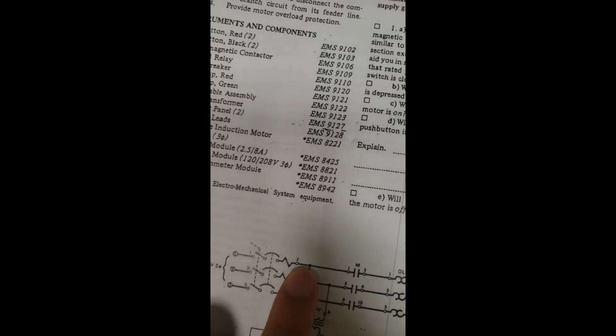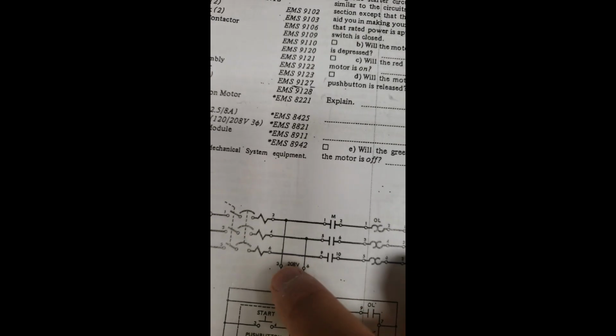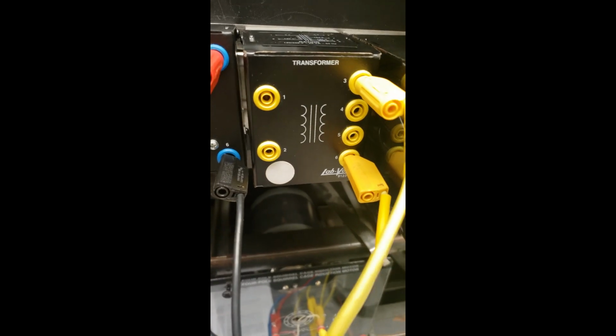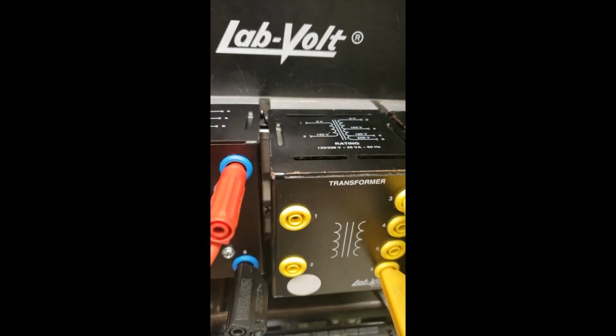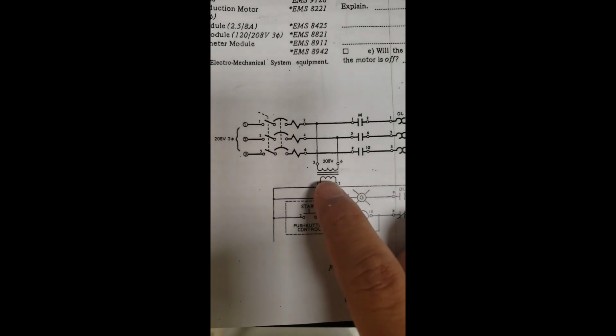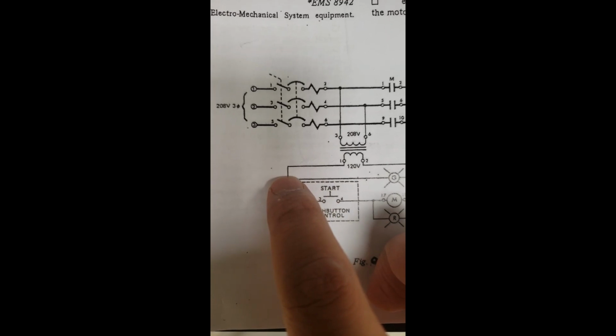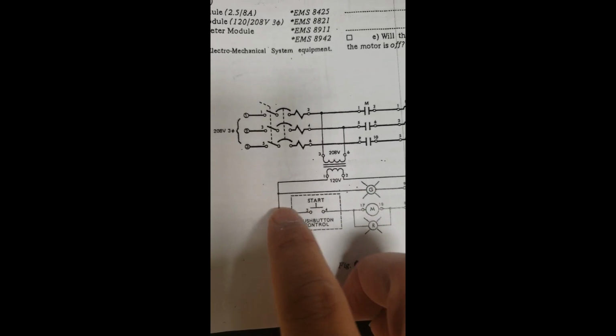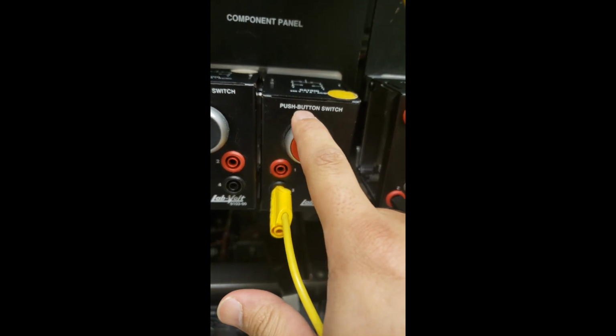Then from 1 and 5 of the contactor, or 2 and 4 of the circuit breaker, to the 3, 6 of the transformer. I took it from here, of the contactor, 1, 5, this one, it will go to 3 and 6 of the transformer. From 1, it goes 2 wires, 1 to the green light. The other one is to 3 terminal of the push button. So we will consider it the start push button.